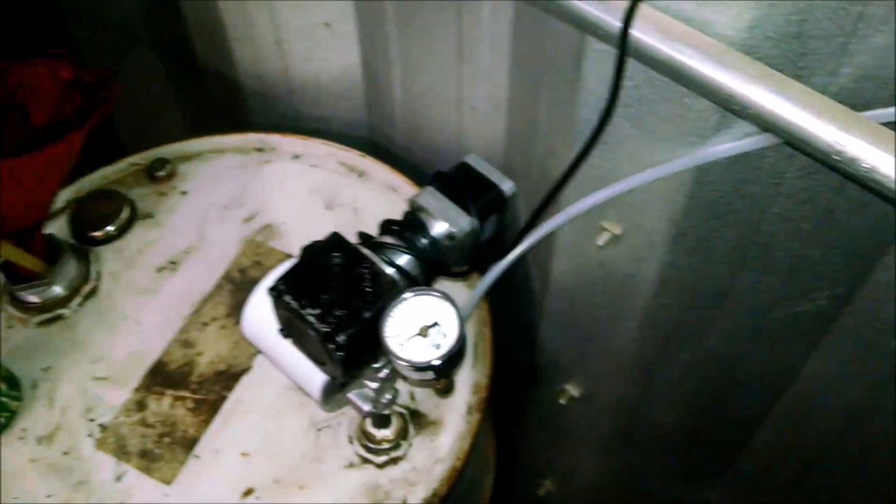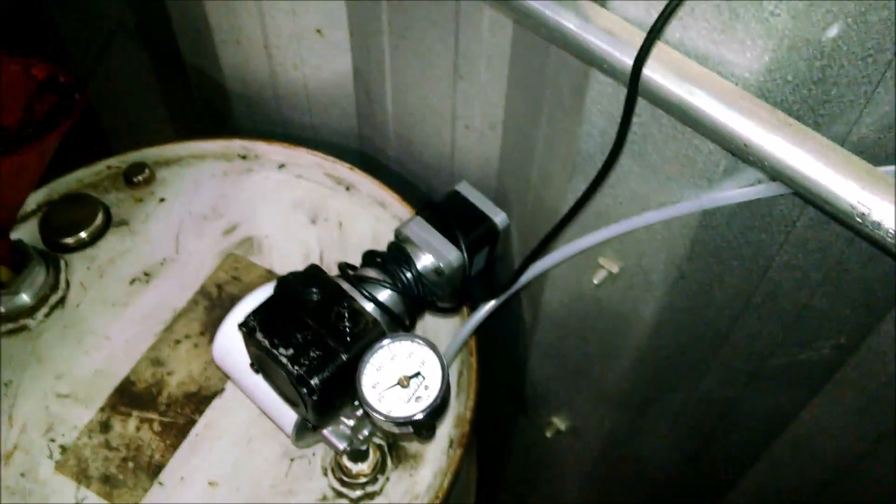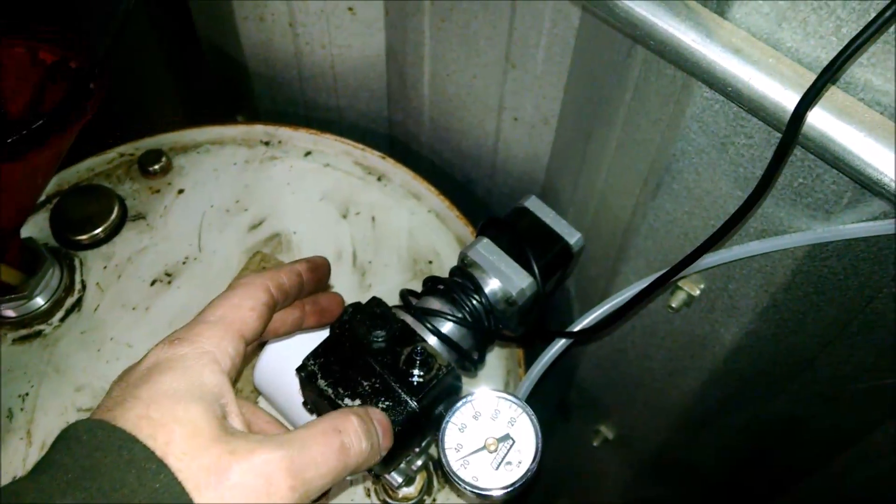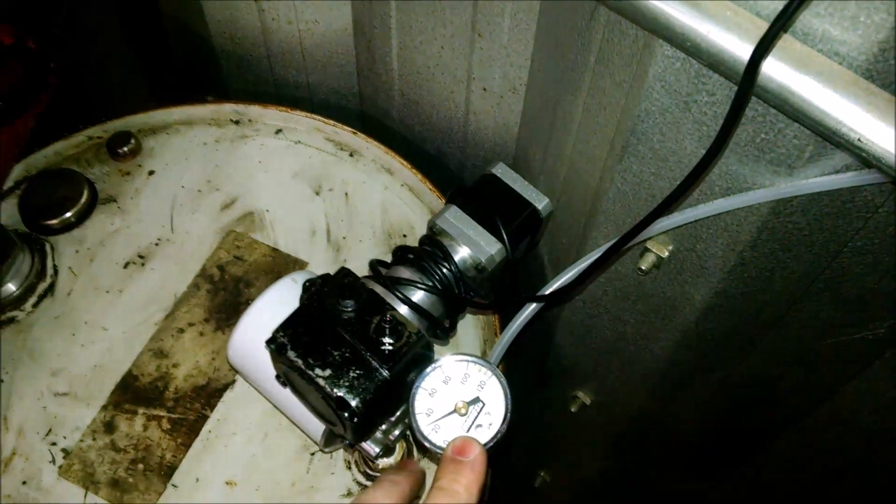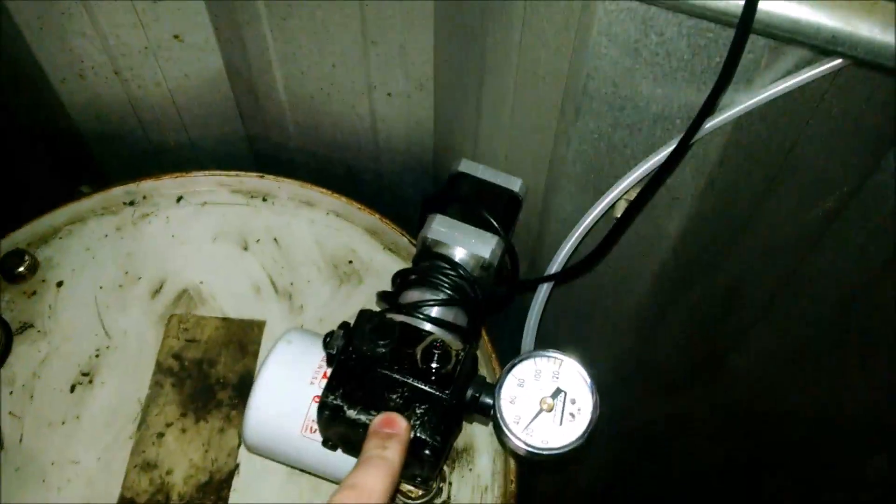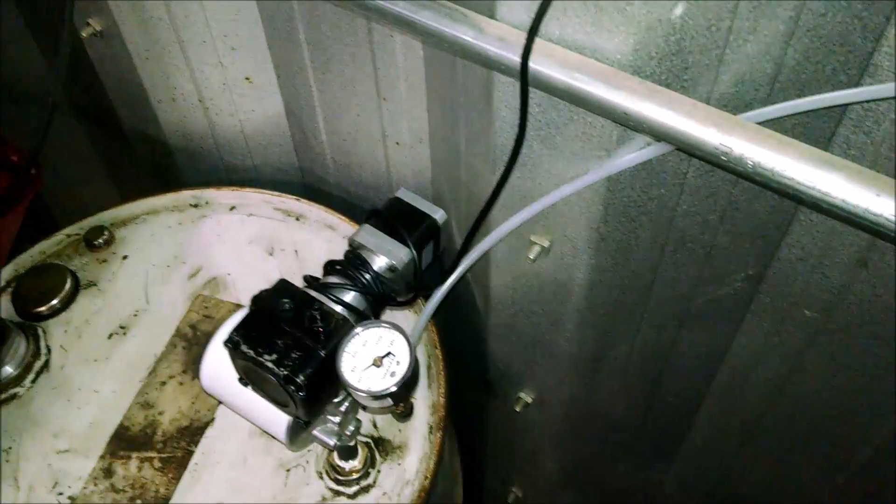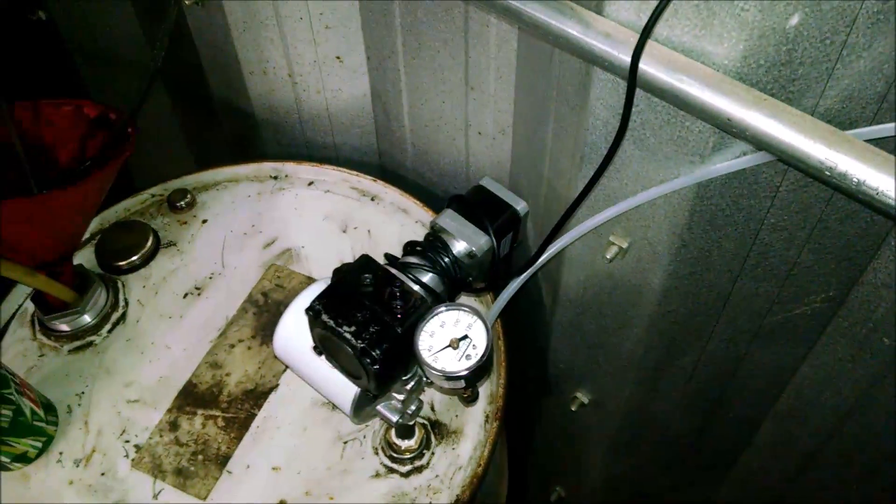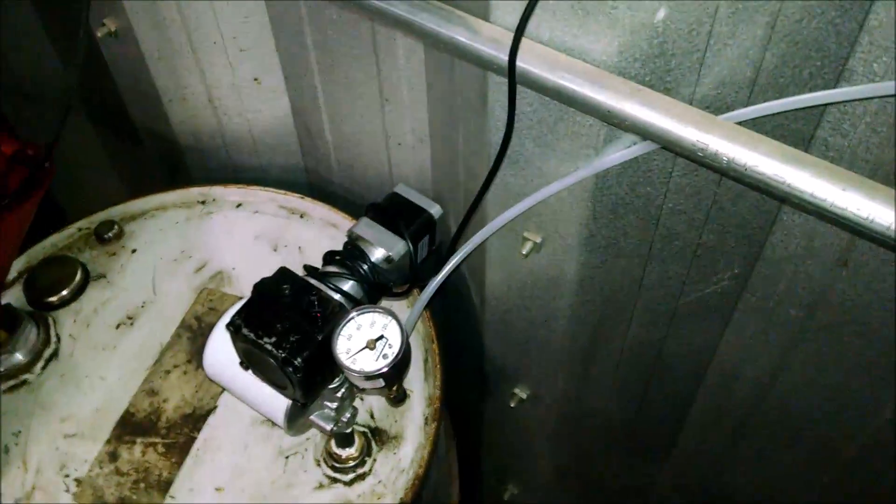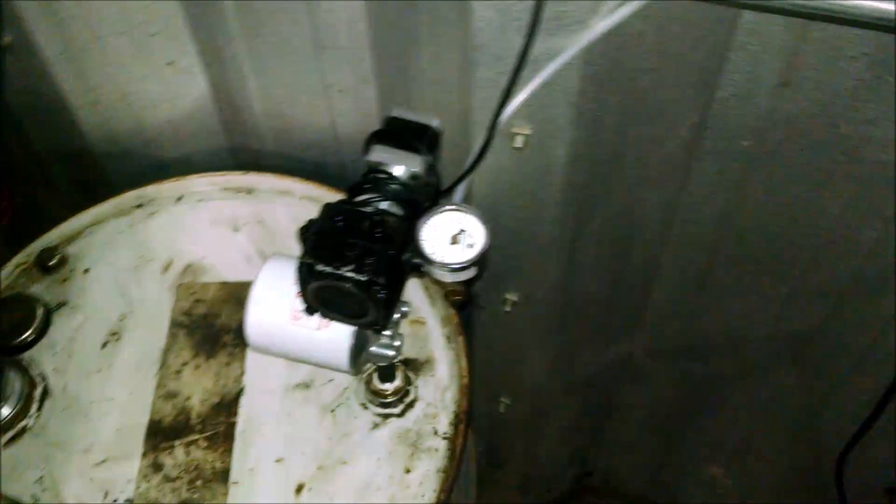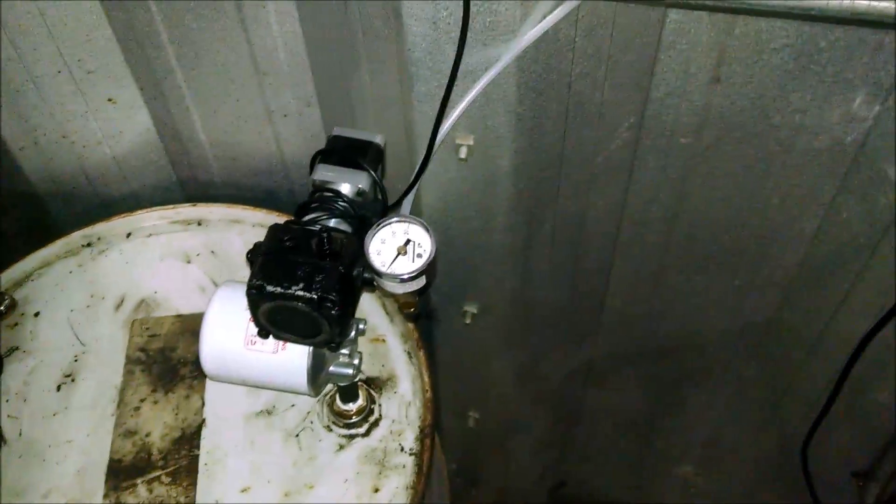So right now, I don't have this actually opened up. So this regulator, I put a lighter spring in here, it only runs about 20 psi at deadhead. It can put out 100 to 120. But so the motor's just running out of steady speed. Somewhere around, I think it's anywhere from about 80 RPM down to about 20 is the flow rates I have right now. And I don't know what that correlates to. I know this nozzle runs approximately a gallon an hour. So you've got a fairly decent amount of heat, especially as little time as it's been out in the shop.